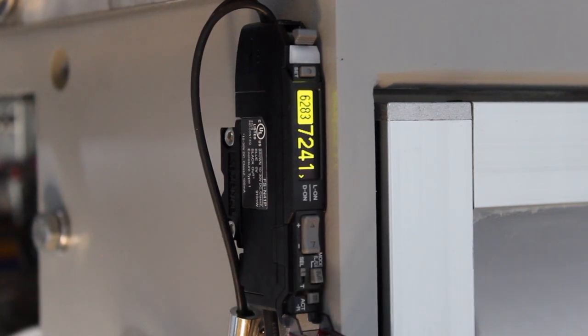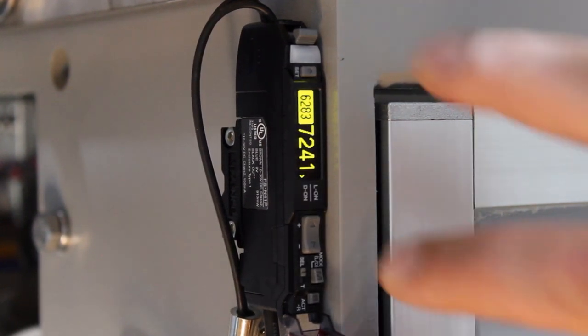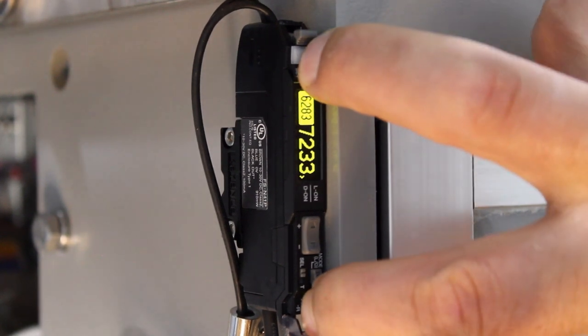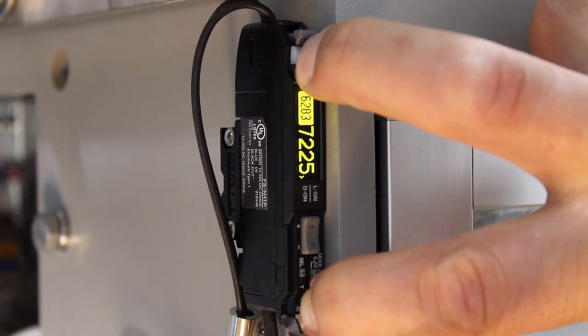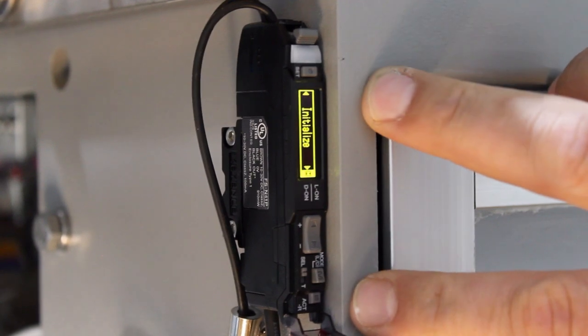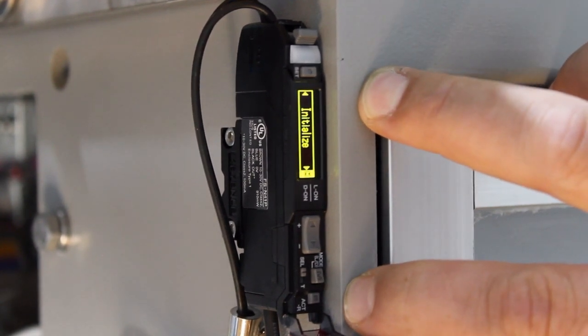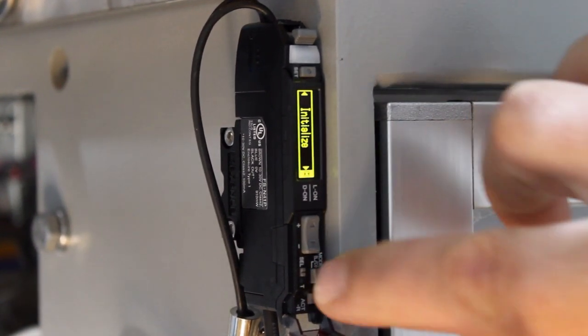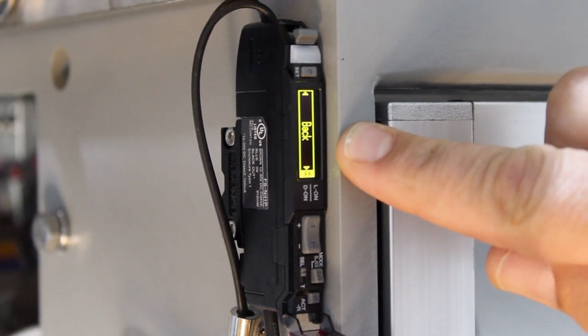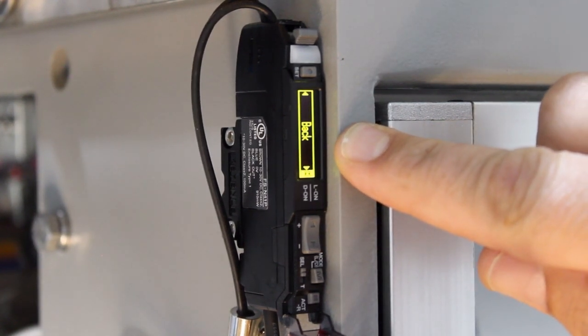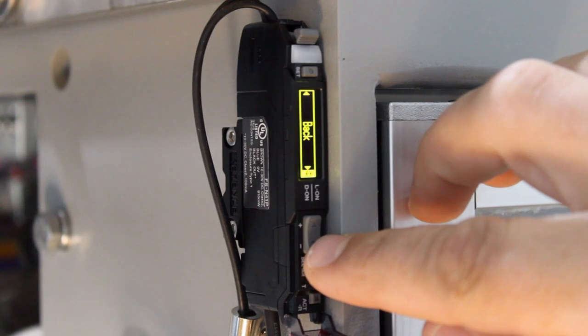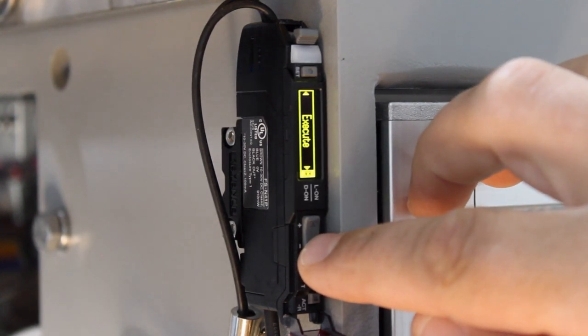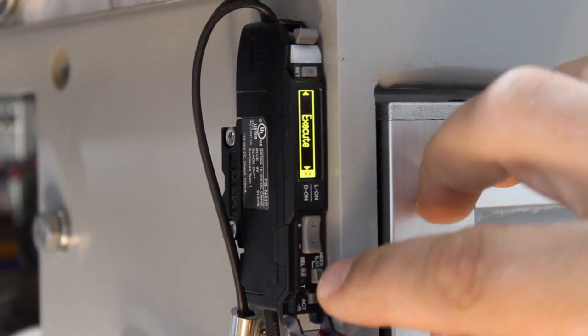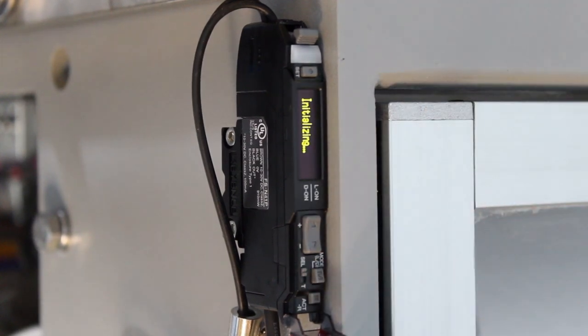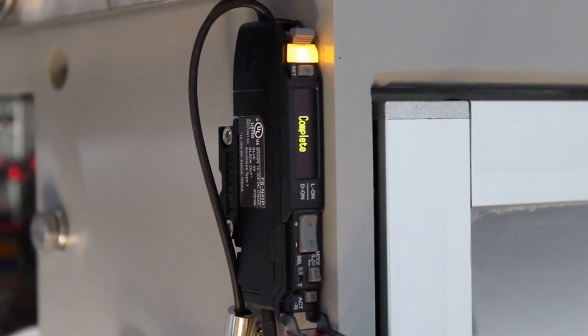In order to initialize the sensor, hold the set and ACTR buttons at the same time until initialize is displayed. Then we're going to hit the button marked M, and the word back will come up on the screen. And we're going to press the right button until execute comes up on the screen, and we're going to press M again. It'll say initializing and then complete.